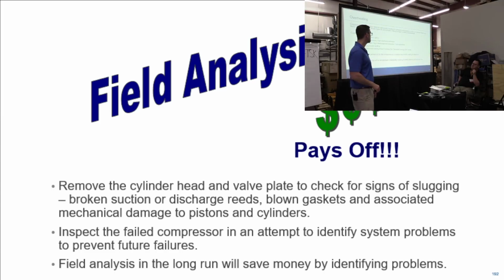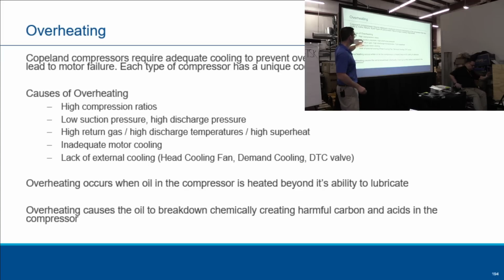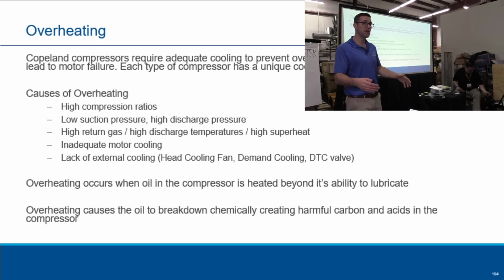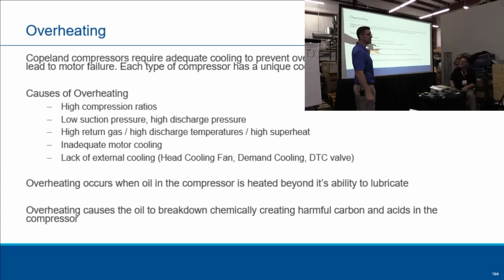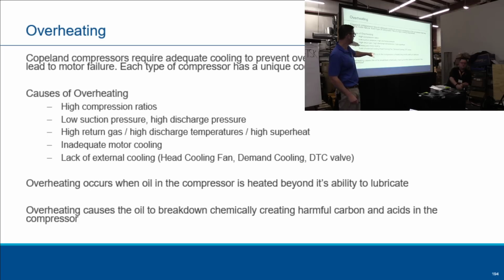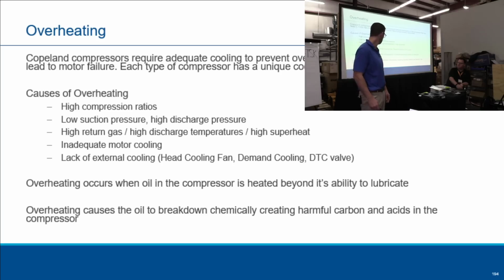Okay, overheating. Causes of overheating: high compression ratio, like Don's been saying, low suction, high discharge, high return gas, high discharge temperature, high superheat, inadequate motor cooling, lack of external cooling, head cooling fan, demand cooling, DTC. So sometimes you need to add a head cooling fan to a system, or demand cooling if you're retrofitting gas. Overheat occurs when the oil in the compressor is heated beyond the point where it lubricates. Okay? Overheating caused by oil breakdown chemically creates harmful carbon and acids in the compressor.